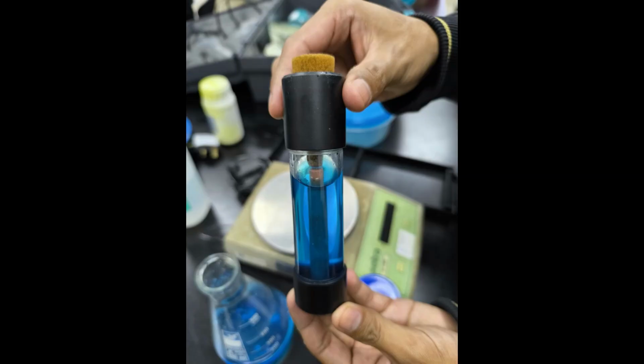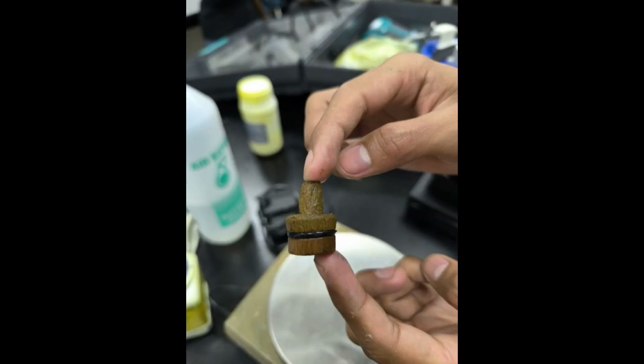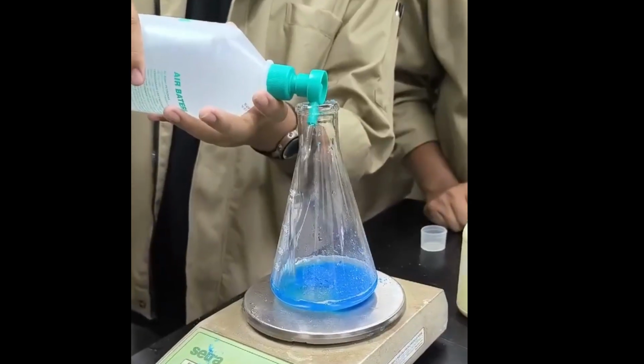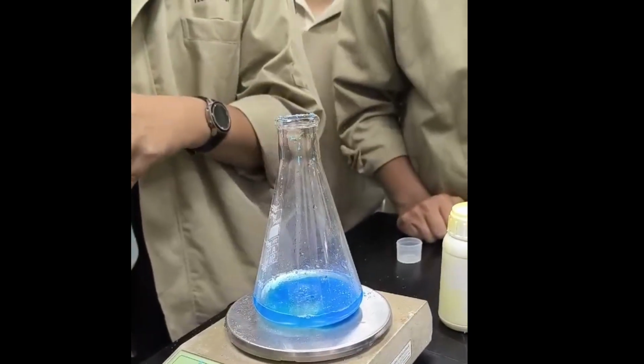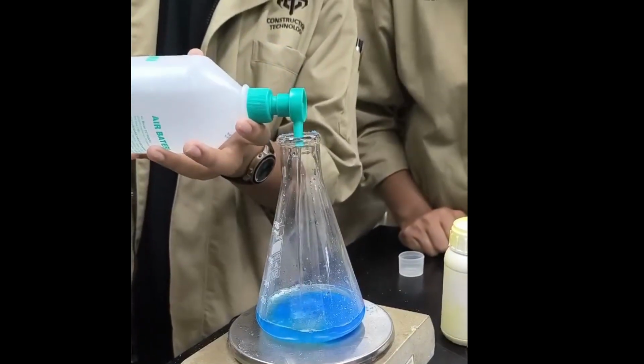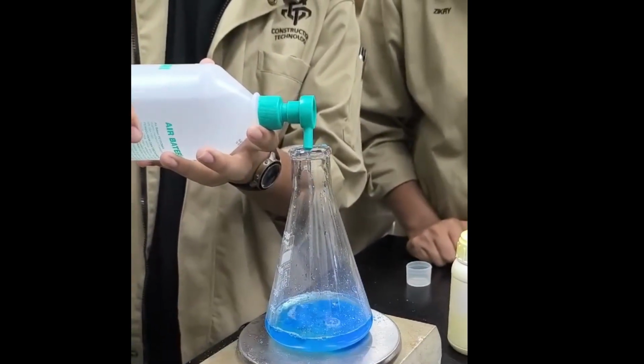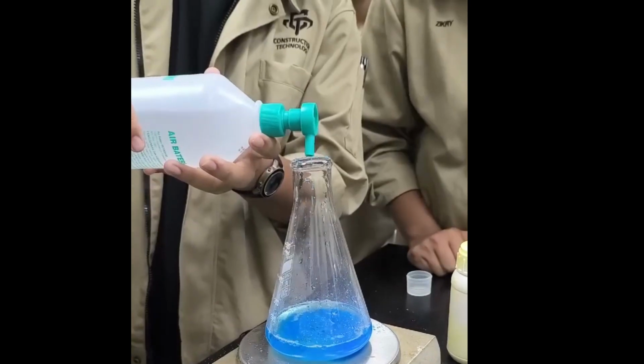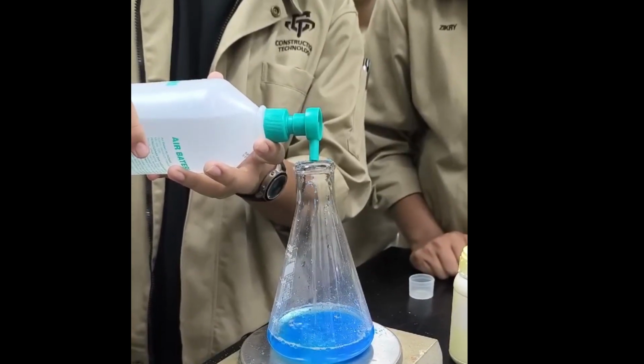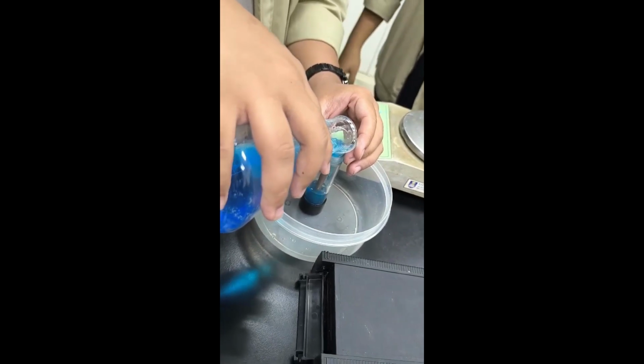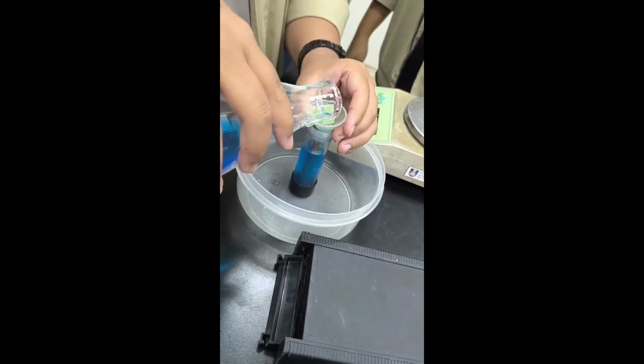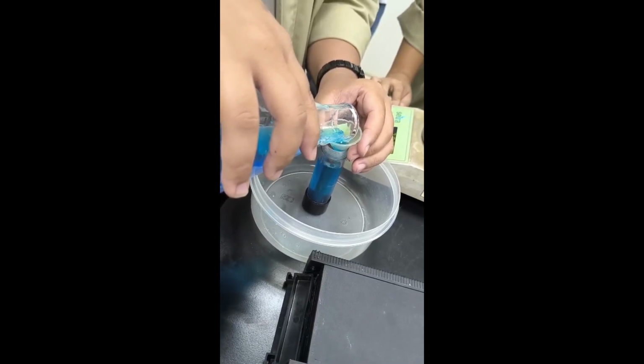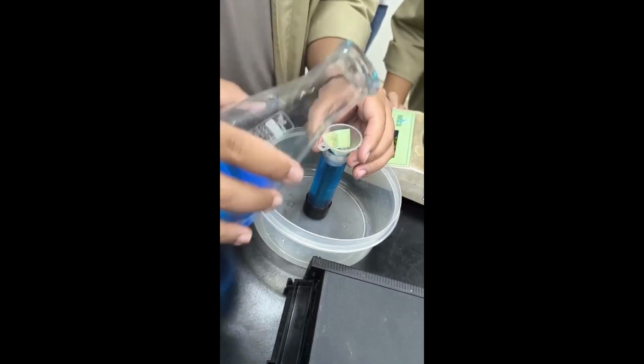Procedure. Prepare the electrode's rod. Electrode. Before filling, remove the red cap with the wooden plug and soak it in water for about an hour to allow the wood to saturate and swell. Copper sulfate solution. Prepare a saturated solution by mixing 40 units by weight of copper sulfate with 100 units by weight of distilled water. To ensure the solution remains saturated, add an additional teaspoon of copper sulfate crystals into the electrode.